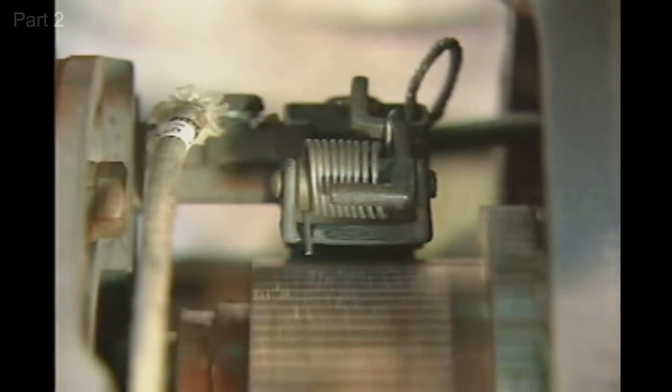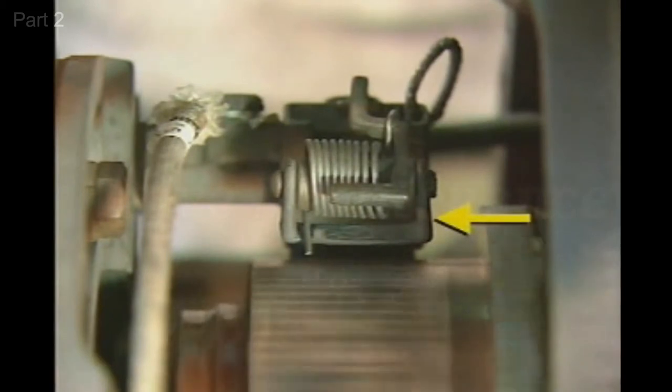To do their job properly, the brushes must make full flat contact with the commutator at all times.